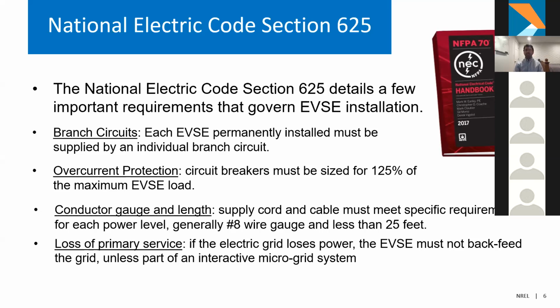So if you imagine in your home, sometimes the kitchen lights are separate from, say, the bedroom lights. And if you go to your breaker box and turn off one of the breakers, all the lights in, say, a bedroom would go off, or in the kitchen would go off. Each one of those is referred to as a branch circuit. So each circuit breaker protects the branch circuit, and that's sort of how they're designated. If an EVSE is installed in your home or at a facility, each one of those must be installed on a separate branch circuit. So essentially for every charging device at your home, there will also be a corresponding circuit breaker in your circuit panel.